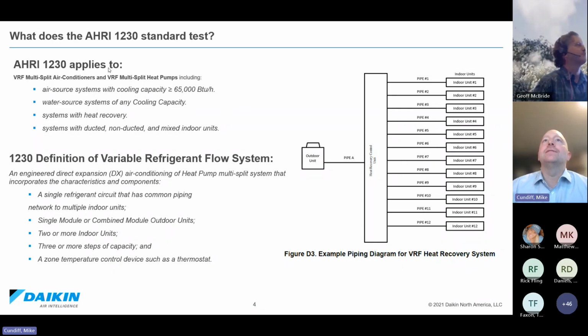AHRI 1230 applies to air source systems with cooling capacity greater than 65,000 BTUs. So this is not for mini splits. This is for larger capacity VRF systems only. It applies to water source VRF systems with heat recovery. And then there is a ducted, non-ducted, and mixed indoor unit component to this. Below left is further definition of what constitutes a variable refrigerant flow system, and then on the right there is a diagram that shows that as well.